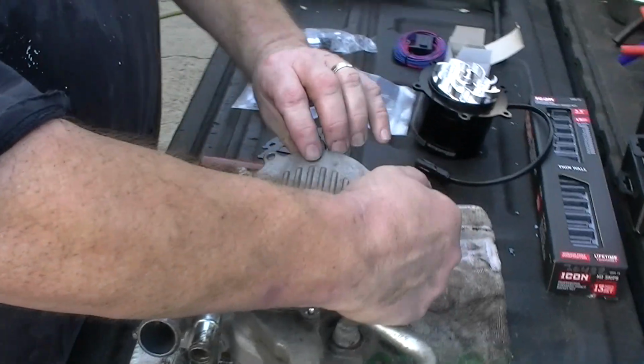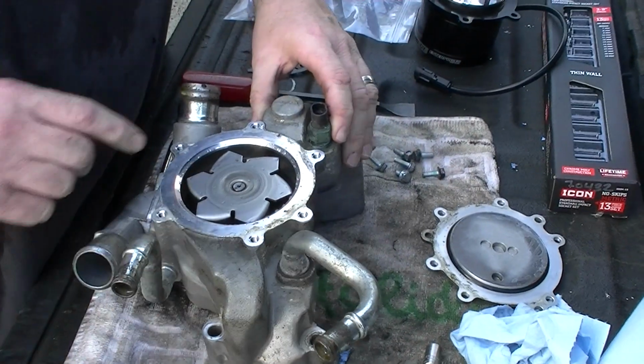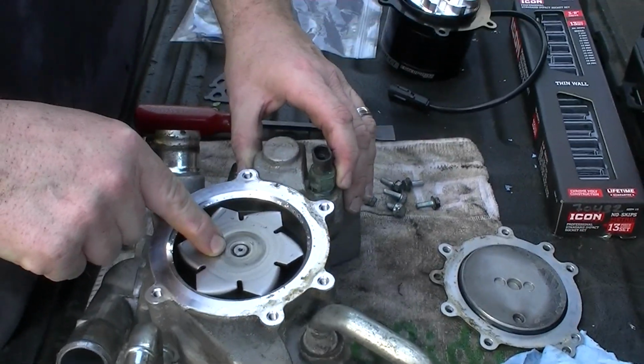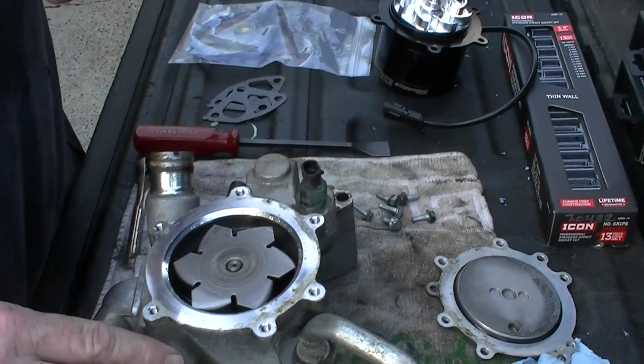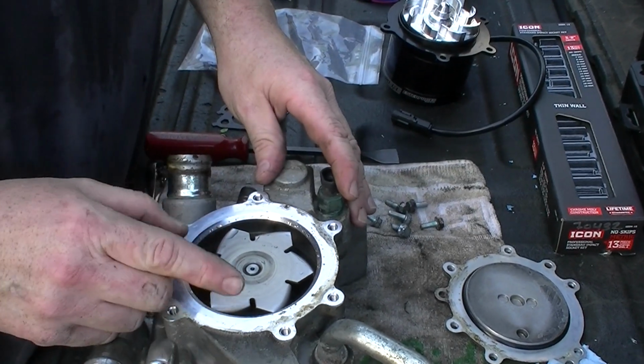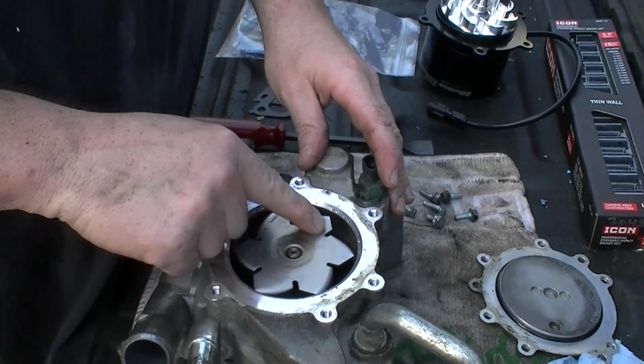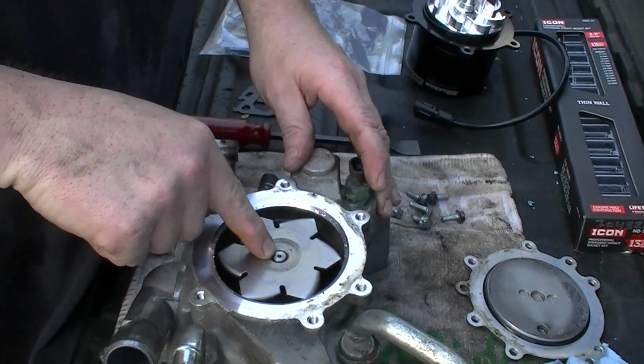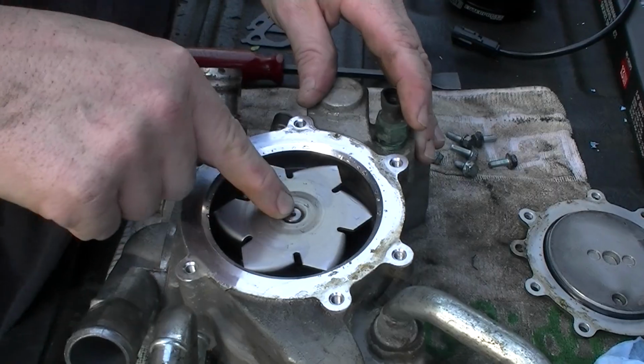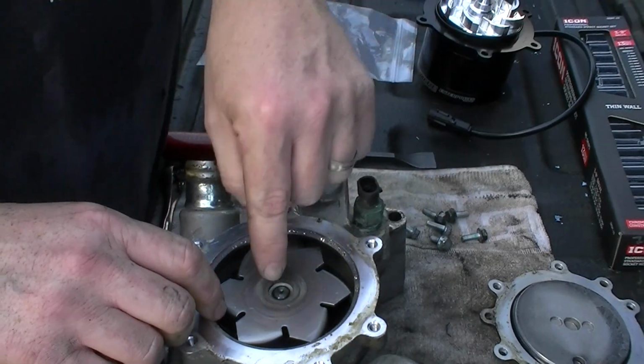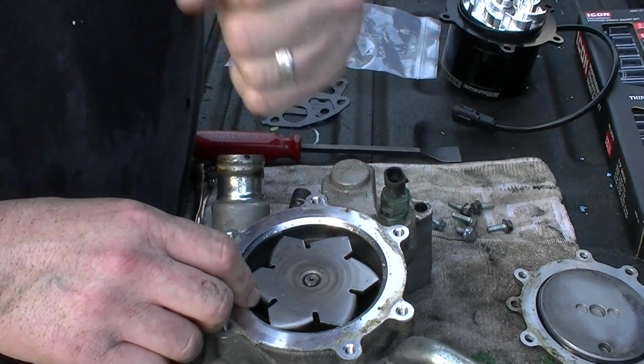Once that's removed, this comes off, and this is what we're going to be pushing out. You can do this two ways: with a hammer and a punch, or press it out. I'd recommend a punch. You don't want to put pressure on the impeller - you want to put it right in the middle on the drive spline, and either press or punch it out with a hammer.